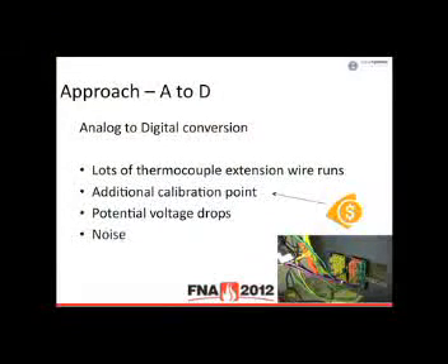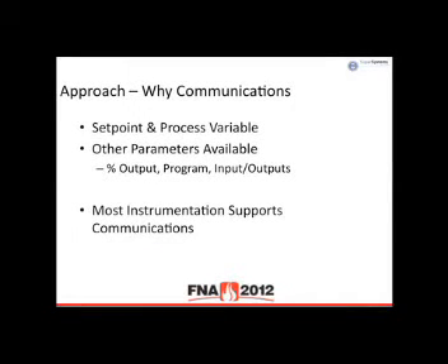All right, so now you have that component that you have to look at. The other thing when you look at analog to digital, as far as gathering that information, you have to look at long thermocouple extension wire runs. I've seen facilities that tie all of their load sensors and control sensors into one central location with extension wire. It works. It can be done, but that creates a potential for voltage drops as well as noise over the lines. So there's multiple ways to do it as far as getting that information. Another reason to use communications is to get away from that. So you're using communication to talk directly to the control instrument to gather information from there.